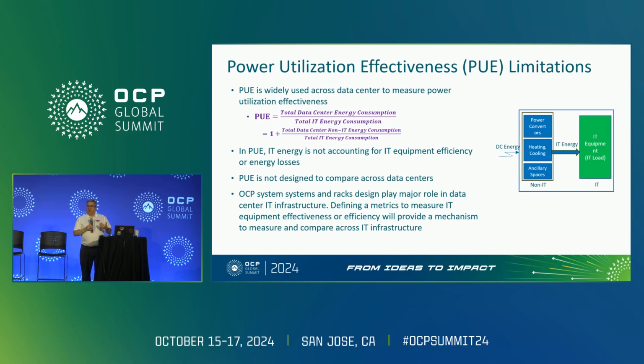But we're also seeing that as folks have realized the best practices for data center design, most of that moving to liquid cooling and other efficiencies, we're reaching an asymptote, a plateau or bottoming of PUE around 1.2. There will probably be ways to continue to improve that, but we're starting to get very, very small gains. There's still a lot that can be improved upon - it just won't affect PUE.